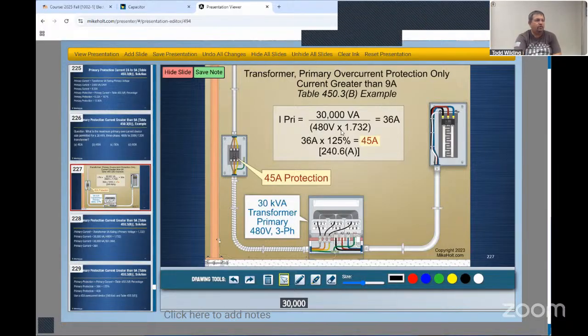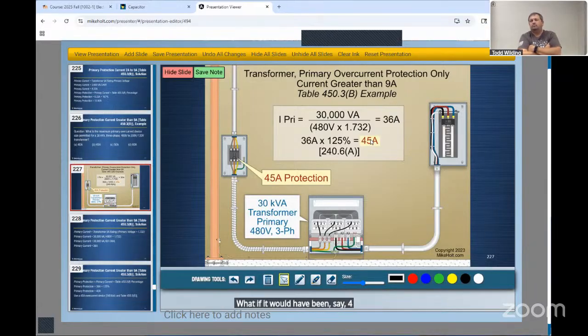30,000 divided by 480. Oh, I got to add that 3-phase in there. Don't forget that. So 480 volt times 1.732. After you divide it, you should get 36 amps. 36 amps at 125% is 45 amps. Is that a standard size breaker? It sure is. What if it would have been, say, 46.5 amps?